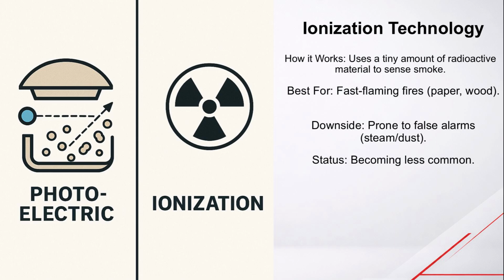The second type is ionization. These use a tiny amount of radioactive material to create a constant electrical current between two plates inside the detector. When smoke enters, it disrupts that current and triggers the alarm. These are very good at detecting fast flaming fires, like burning paper or wood. However, you will see these less and less in commercial systems today. Why? Because they are more prone to false alarms caused by steam, dust, or humidity. Most engineers and inspectors now prefer photoelectric detectors for stability.